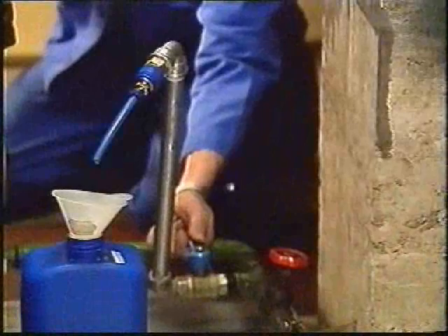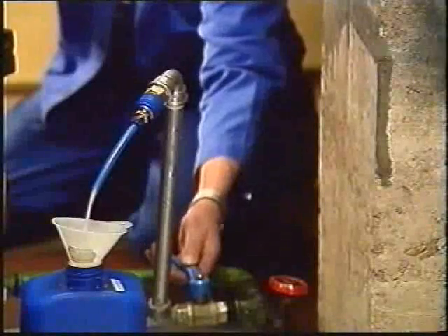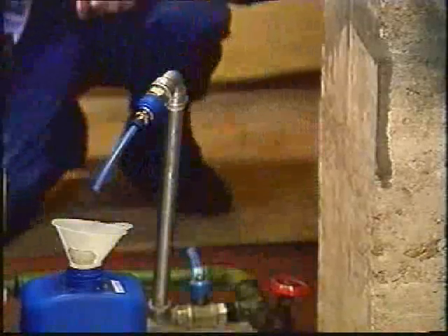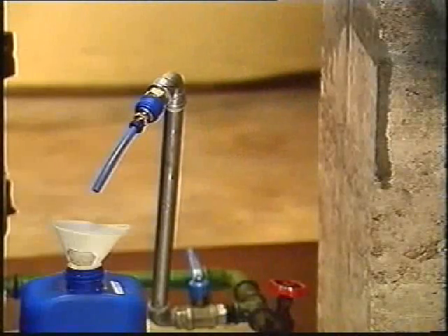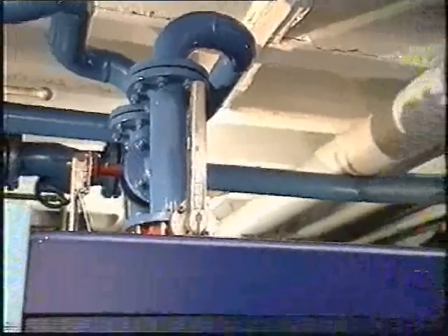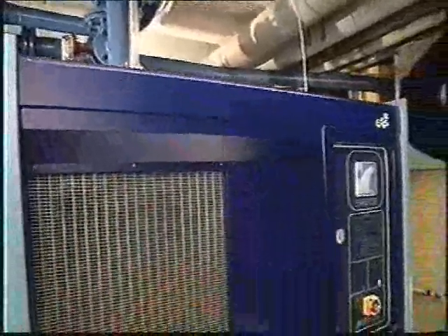In addition, the reservoir helps to cool the compressed air. As the air cools, moisture separates from the air and collects in the bottom of the reservoir. This water must be drained from the reservoir on a regular basis. Not all of the moisture is removed in the reservoir, so in order to prevent corrosion of valves and other components, a dryer is often included in the system.